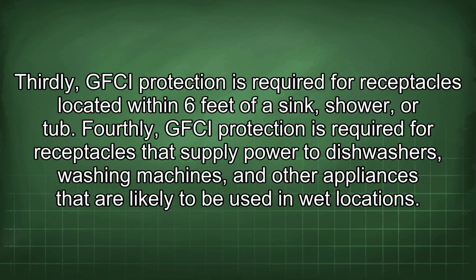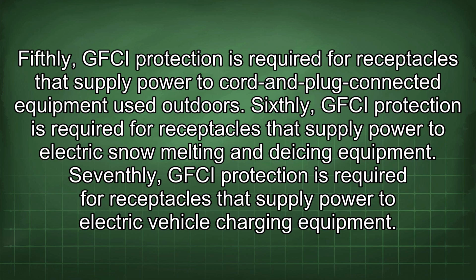Fourthly, GFCI protection is required for receptacles that supply power to dishwashers, washing machines, and other appliances that are likely to be used in wet locations. Fifthly, GFCI protection is required for receptacles that supply power to cord and plug-connected equipment used outdoors. Sixthly, GFCI protection is required for receptacles that supply power to electric snow melting and de-icing equipment. Seventhly, GFCI protection is required for receptacles that supply power to electric vehicle charging equipment.